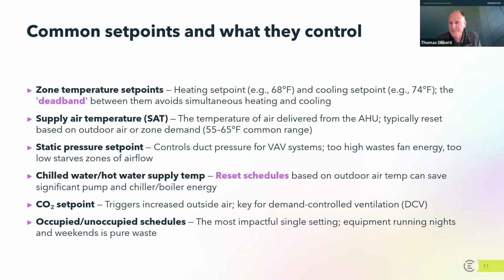So let's talk set points. I wanted to give you some of the most common set points, and you'll see these certainly in the screenshots that are coming up, and start to blend in some new terminology or some words that are really critical to your understanding for how these building automation systems function. So first, and maybe the most obvious thing, is zone temperature set points. So heating and cooling set points, and I've given you a couple examples here of 68 degrees Fahrenheit for heating and 74 degrees Fahrenheit for cooling. Those are numbers that you'll see in a lot of systems and numbers that you should expect to see.